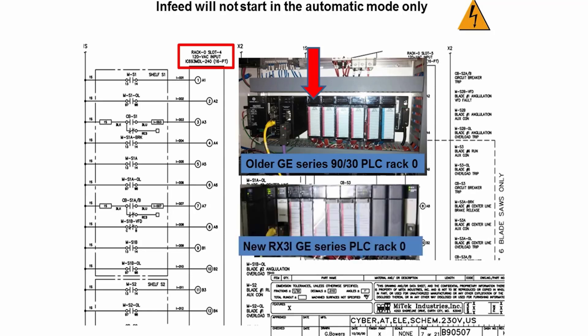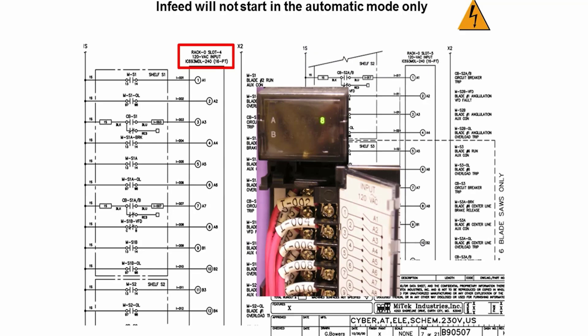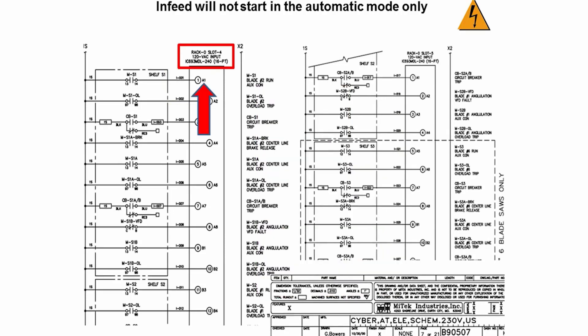If you have the new RX3i GE PLC system, the power supply is in slot one. If you are confused about the slot number, open the wiring cover door and look for wire numbers such as I001, I002 as shown on the drawing — this way you are assured you have the correct input module. The LED input indicator for blade number two run auxiliary contact is A1, and for blade number one run auxiliary contact it is B3. When those two motors are running, those two LED indicators should be lit.